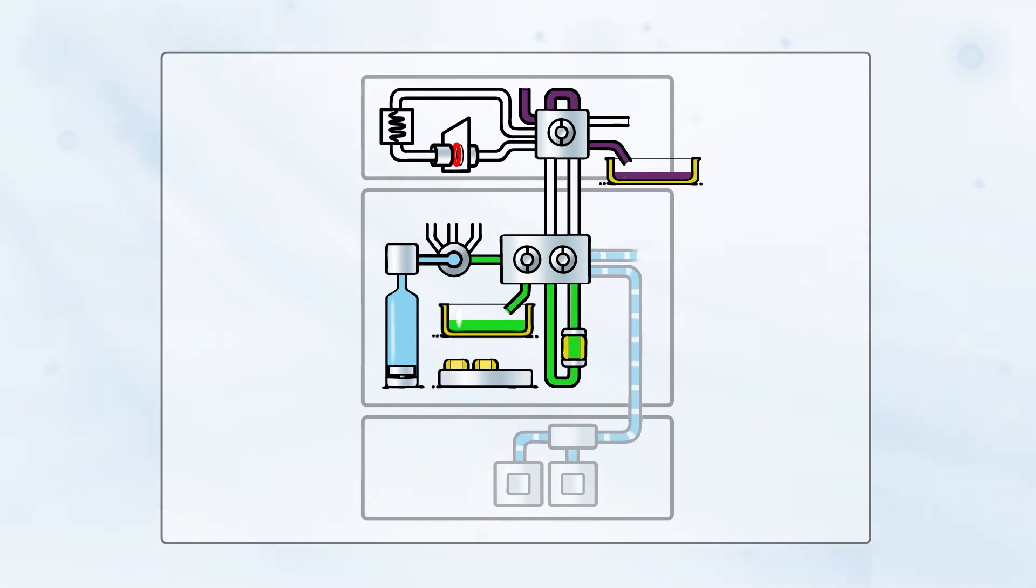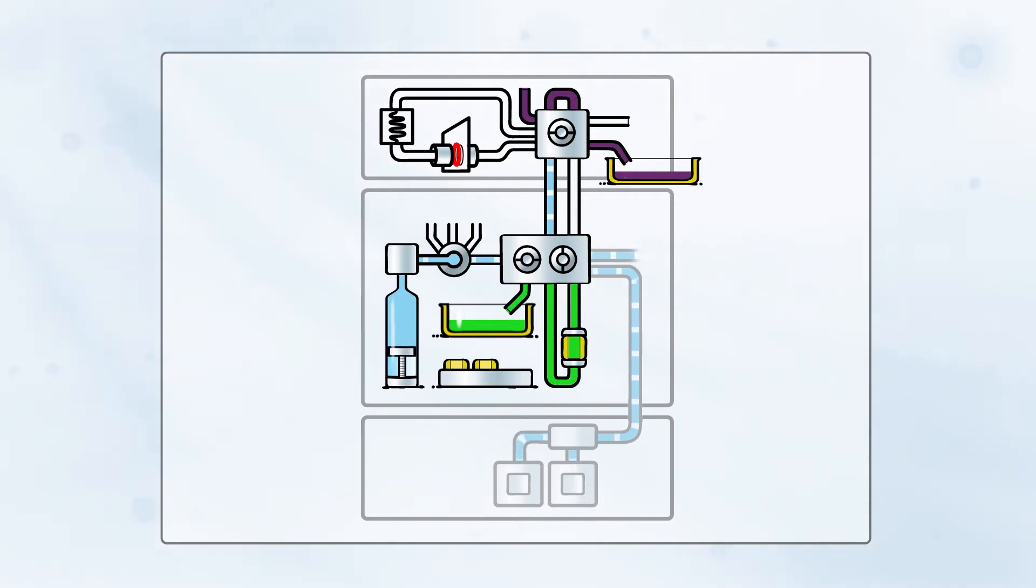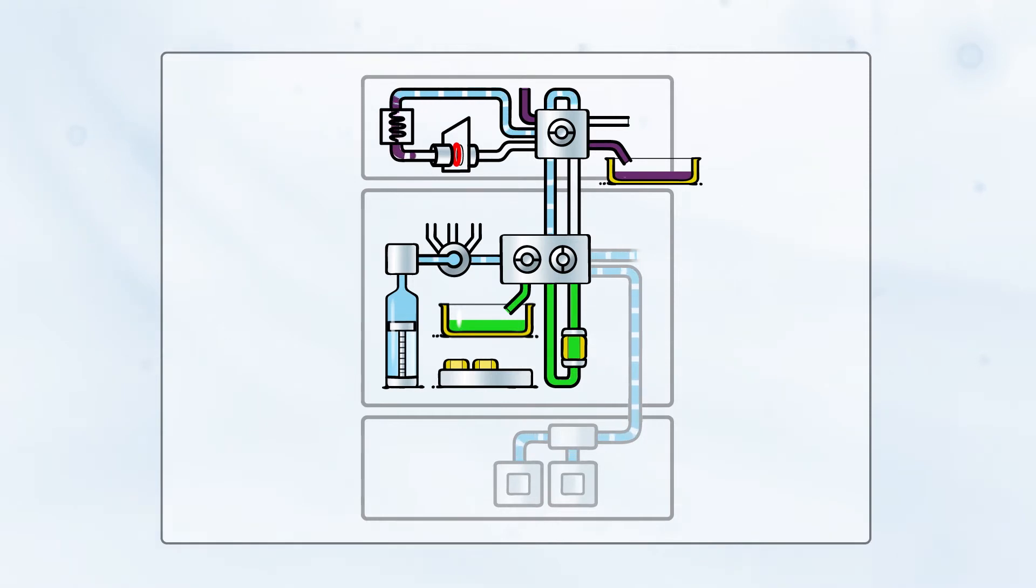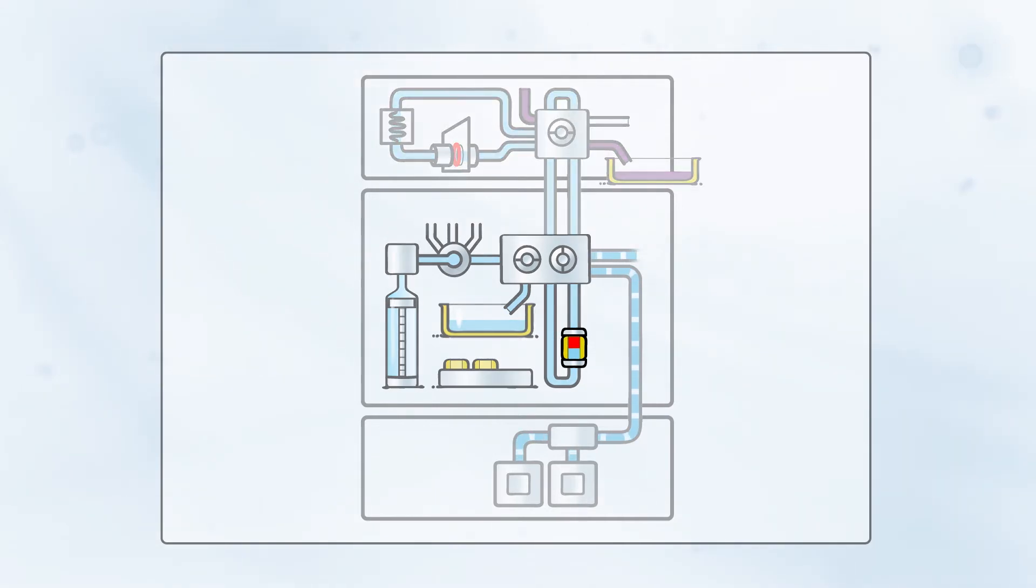The system is now ready for desorption and extraction. Valves are switched to position the loop and the card clamp into the desorption flow path. Desorption solvent, delivered by the syringe, carries the internal standard through the bloodspot while desorbing the constituents. Both the internal standard and the analytes from the bloodspot are subsequently trapped on the SPE cartridge.